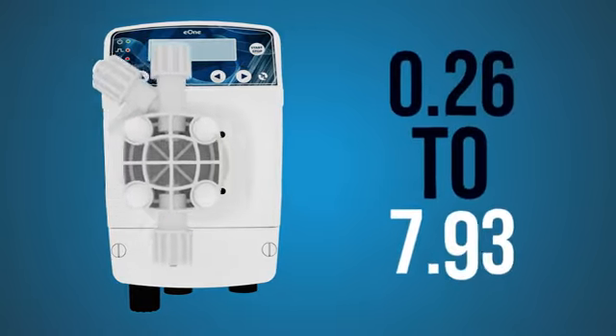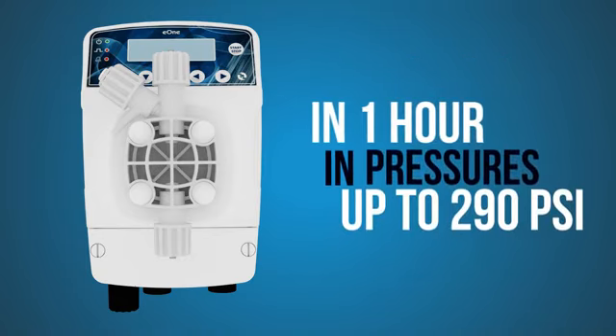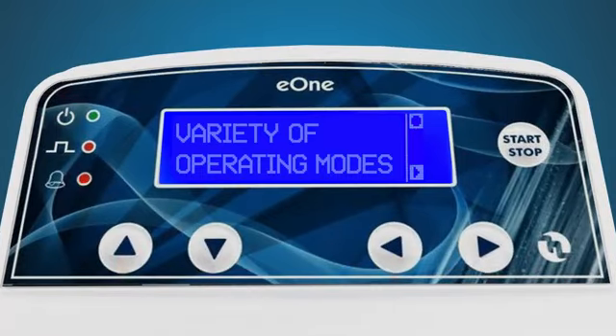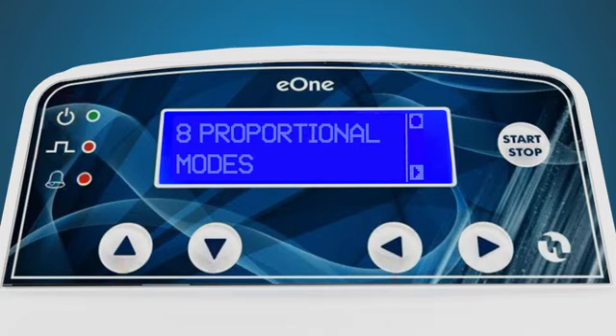It can dose from 0.26 to 7.93 gallons of chemical per hour, at pressures of up to 290 PSI. The eOne MF offers a variety of operating modes, ranging from digital manual operation to eight different proportional modes.